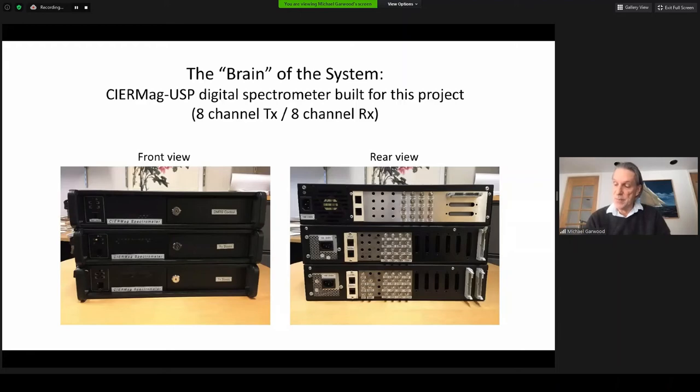The integrated development environment, or IDE, makes use of modern software development tools for creating MRI methods, also known as pulse sequences. This spectrometer is currently interfaced to a whole-body 1.5-Tesla scanner at the CMRR at the University of Minnesota, where it's being used to acquire images and test system components.